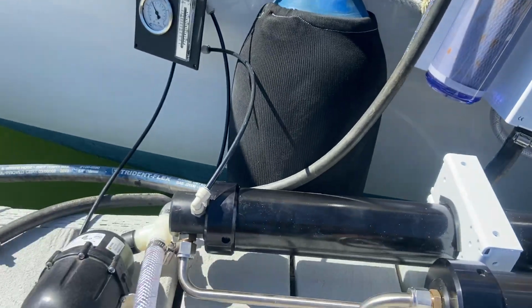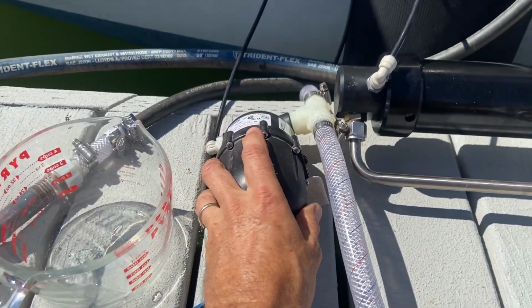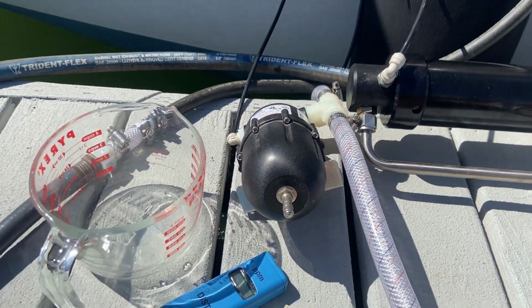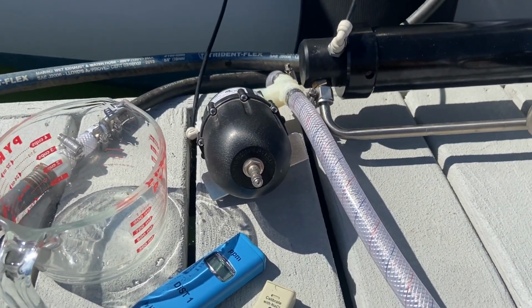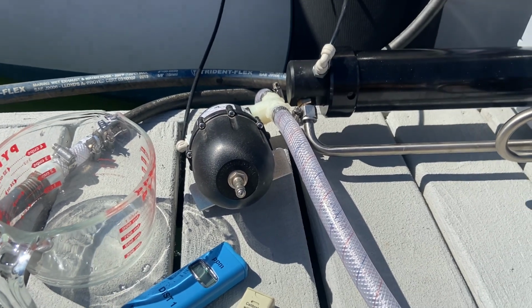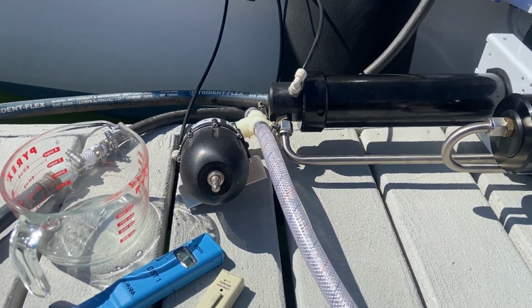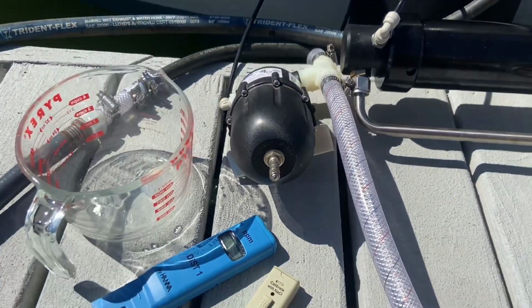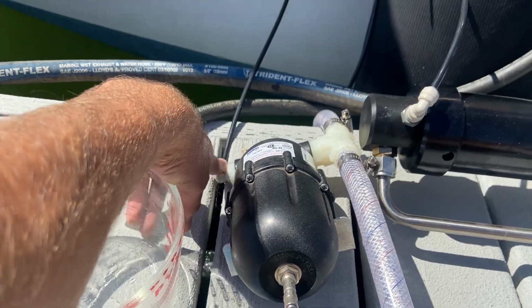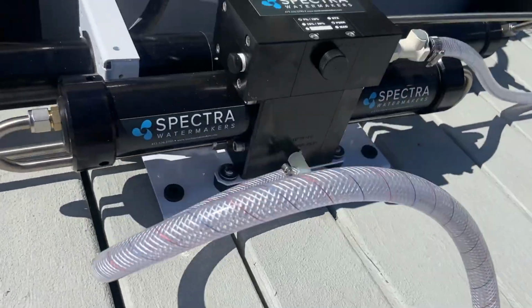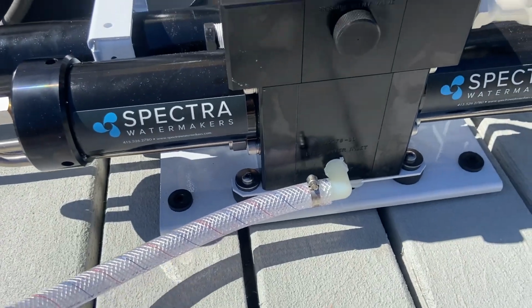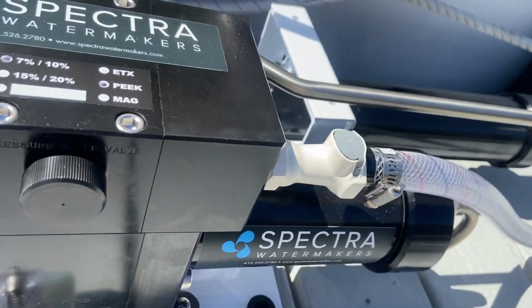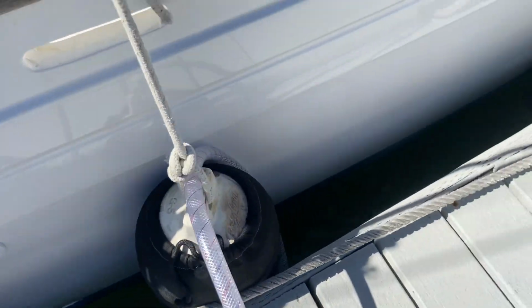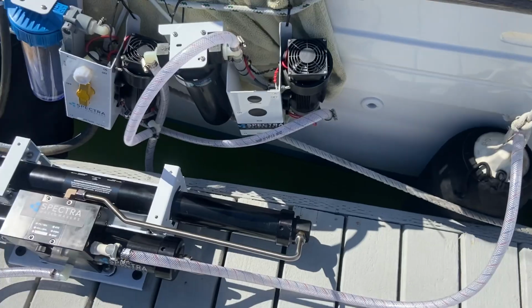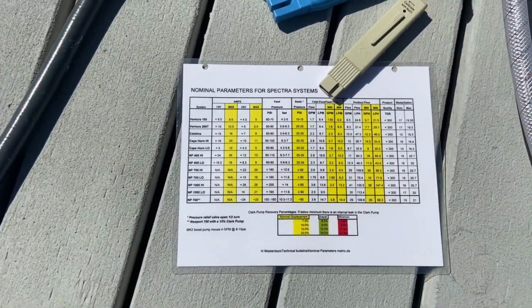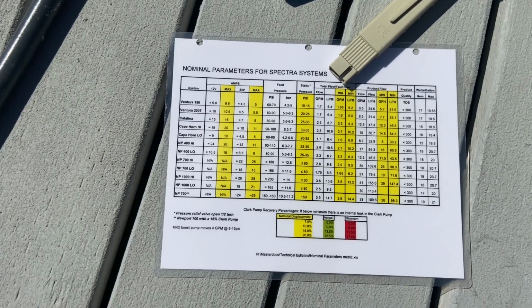Our next stop is an accumulator tank. This is just to take the pressure spikes out of the system from the Clark pump. You can see how it twitches every time the Clark pump changes direction. If you have enough hose, it'll do the same thing, but they use the accumulator tank on all systems. It's also a convenient place to connect our feed pressure gauge. And then the final stop is the feed water inlet into the Clark pump. Then the brine discharge, I'm just using the brine discharge service hose and sending all the brine back in. I already did a total flow test, and everything's performing exactly within spec per Spectra guidelines.